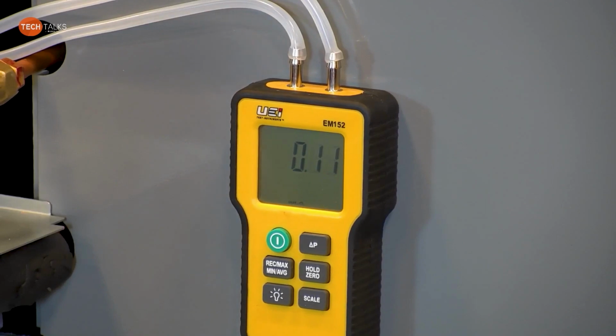It takes a minute for that blower to get rocking and rolling. Still ramping up. I don't know if you guys just heard that through my microphone or not. The one thing that's nice to know: the reversing valve is energized in heating mode on all GREE's equipment, okay?